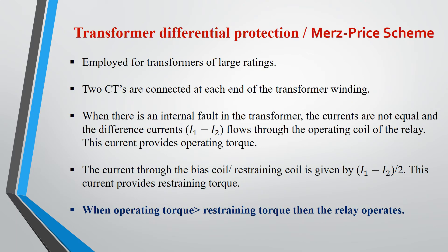The Merz-Price scheme is employed for transformers of large ratings. As the name suggests, differential protection responds to the vector difference between two similar actuating quantities. Two CTs are connected at each end of the transformer winding. Pilot wires are connected between the CTs. Biased coils are also present in series with the pilot wires to avoid unwanted operation. When an internal fault occurs, the currents are not equal and the difference current flows to the operating coil of the relay, providing the operating torque.